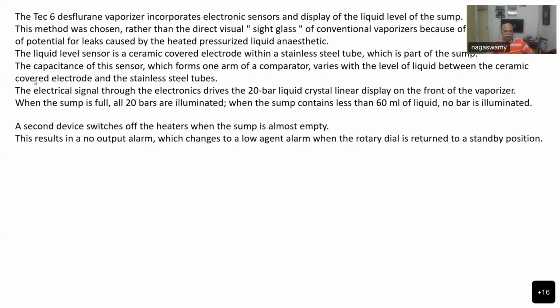A second device switches off the heaters when the sump is almost empty. This is another safety feature. So if the sump is getting dried up, and the liquid is not filled at the proper time inside the vaporizer, the heaters will be turned off so that there is no heating happening to vaporize the liquid. This results in no output alarm.